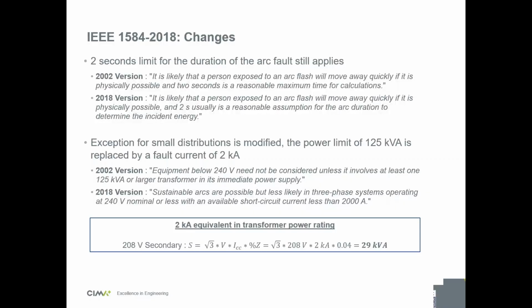A big change is that in the 2002 version, there was a cutoff point at which your distribution is so low power that you stopped needing arc flash studies. In the past version, the exception was if your equipment is below 240 volts and fed by a transformer smaller than 125 kVA. But now it's been changed. It's still under 240 volts, but instead of transformer size, it's now an available short circuit current of 2 kA, so 2000 amps of fault current.